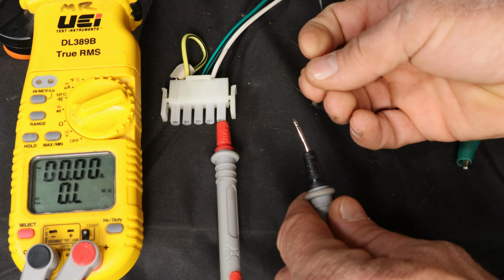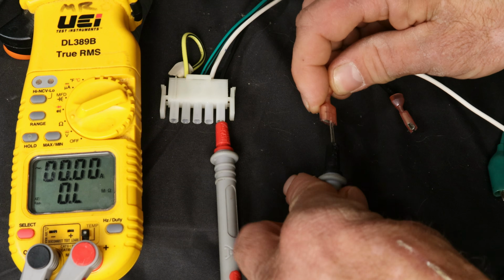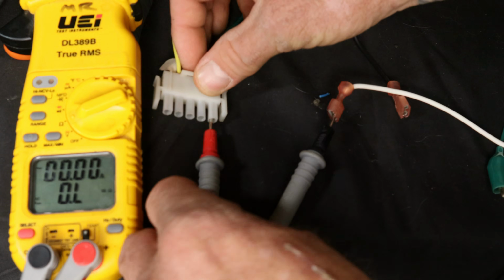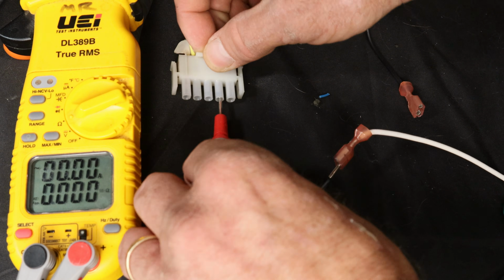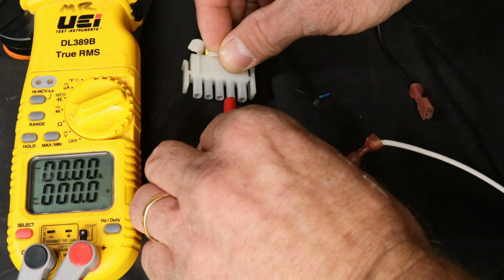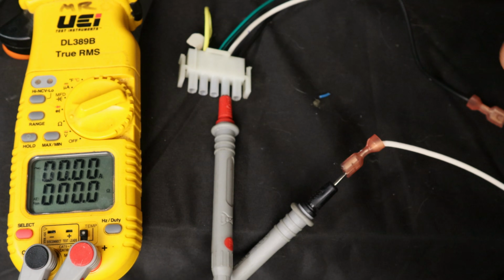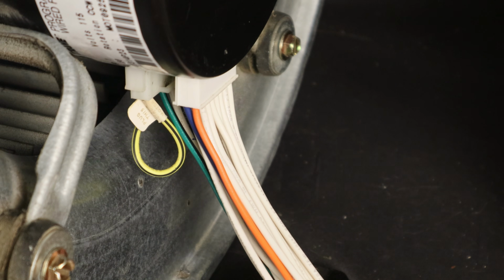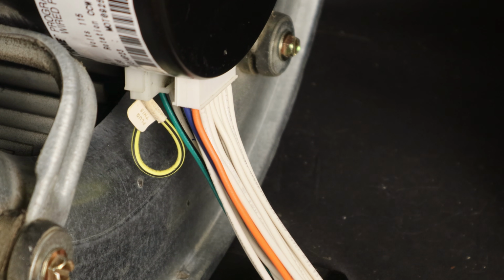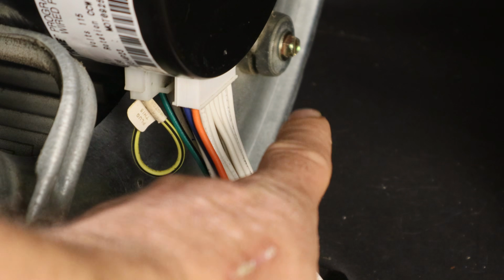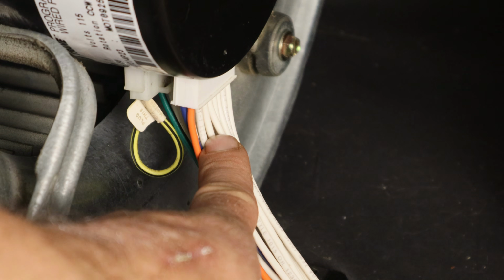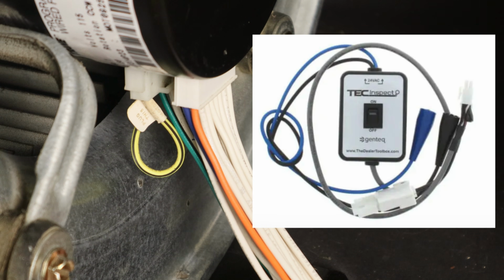So here's our neutral wire. We'll go ahead and put one probe in there. We'll go ahead and switch over to our neutral on the Molex plug, and we should see the same thing. We should see 0. Now at this point, if everything checks out and the motor's still not starting up, what I would do here is I would just disconnect my 16-pin Molex. I would hook up an ECM tester directly to the module itself.